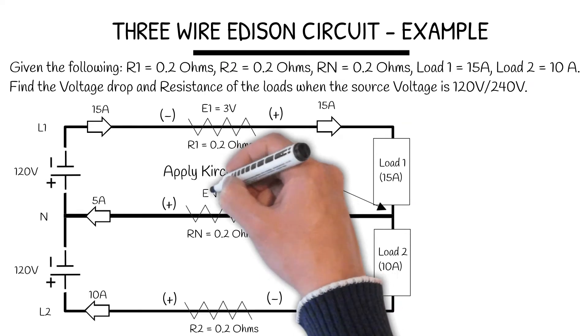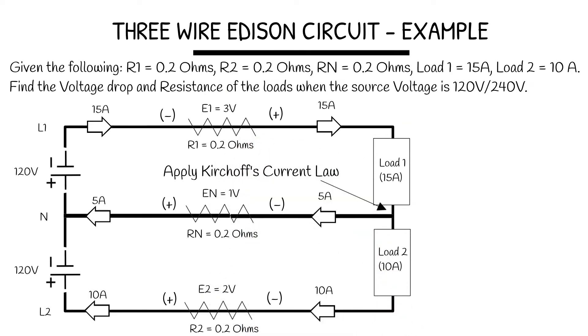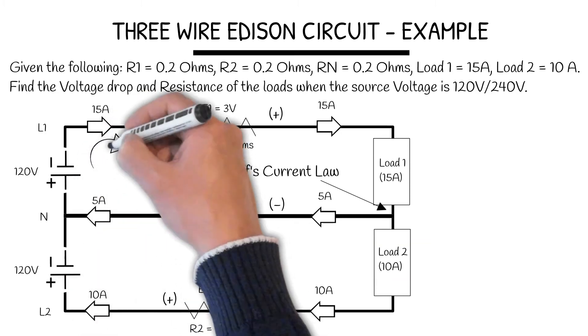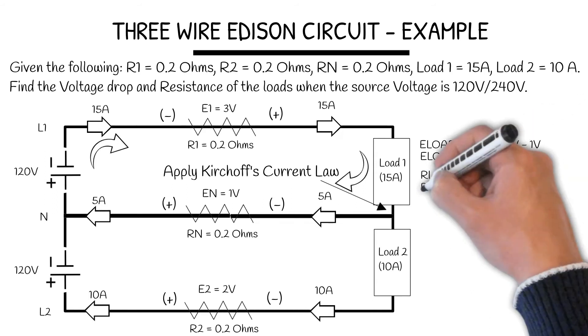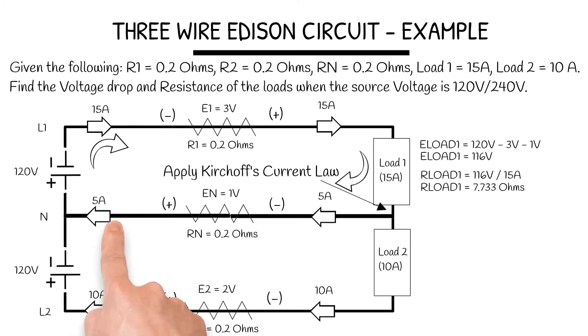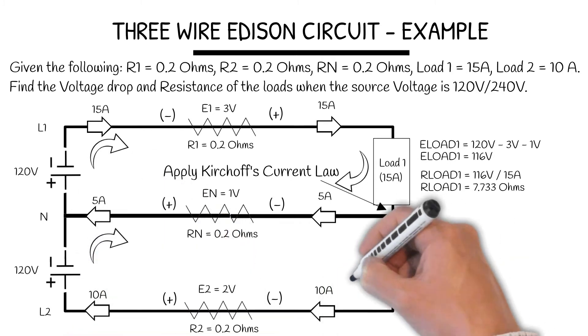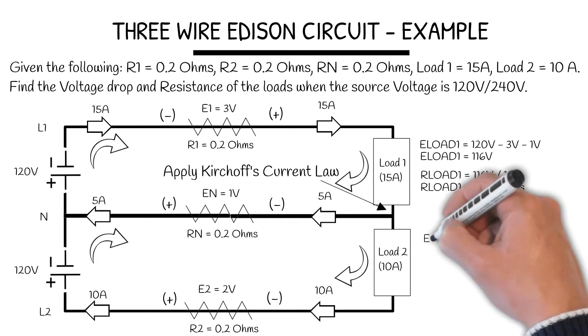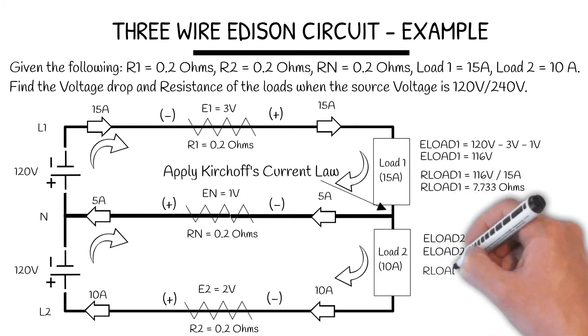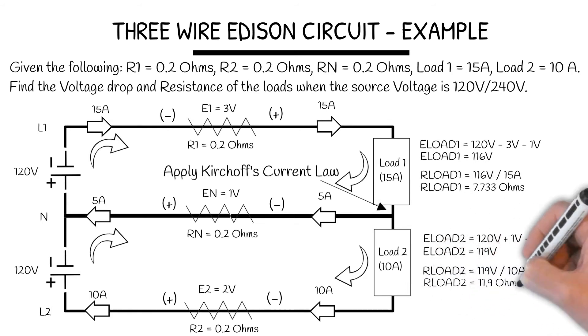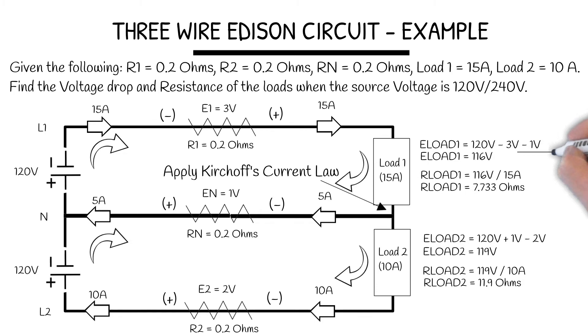Next, we find the volt drop of each resistor. To find the load volt drops, we evaluate each individual loop. For load one: 120 volts minus 3 volts minus 1 volt gives us 116 volts, and load resistance is 7.733 ohms. For the bottom loop, load two: 120 volts plus 1 volt minus 2 volts gives us 119 volts, and load two resistance is 11.9 ohms. Again, the neutral conductor's polarity determines whether we subtract or add the 1 volt.